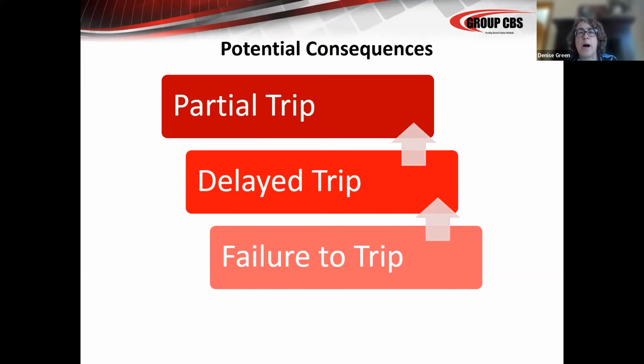Well, if a breaker is operating with a trip unit, you didn't anticipate that either. But your cascading event gets much larger when a breaker doesn't trip. So instead of one feeder tripping one motor control center, you might have the main trip and take out half of a substation, an entire process at a facility. So that can lead to equipment damage. If a milling machine stops in the middle of what it's doing, you're going to have product damage, milling machine damage, tool damage. All of those things can happen when a main trips instead of a feeder.